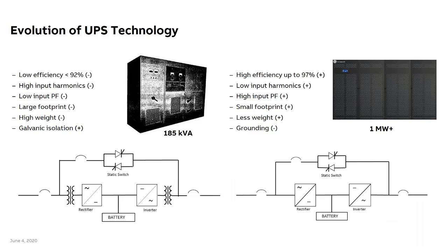And actually this is the picture, which is not great quality, but interesting historically. That's actually a GE UPS from the late 60s, 185 kVA, with a design that's exactly as I just described, based on SCRs, SCR rectifier, SCR inverters. And the single line, the two at the bottom, the one on the left is what the UPSs would have looked like back in the 60s, 70s, 80s actually, and even a little later than that, with transformers and what could have been shown, but not as detailed here.